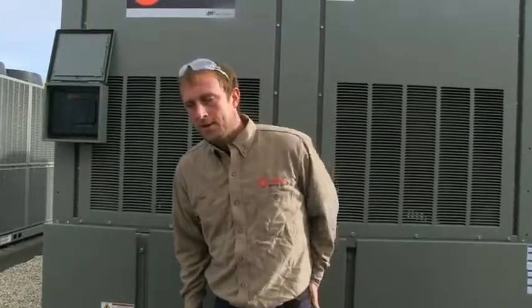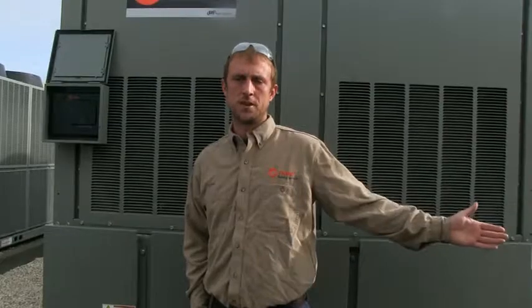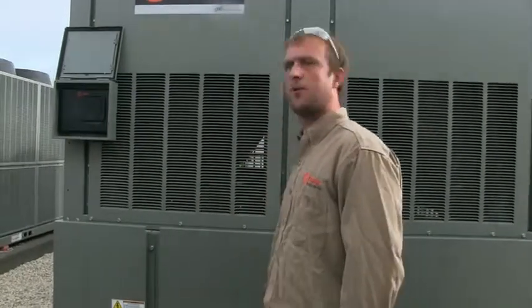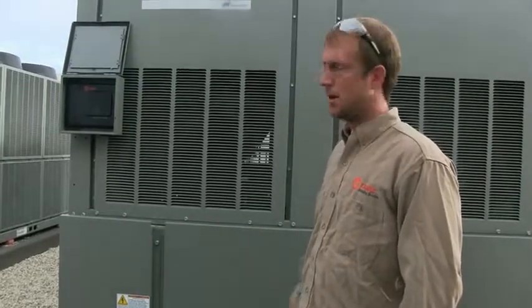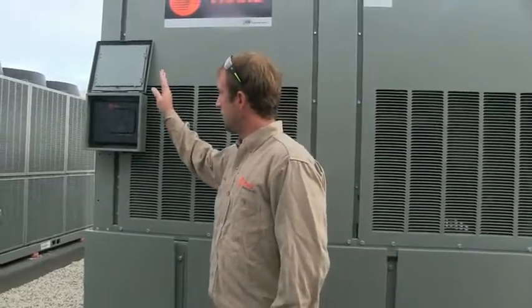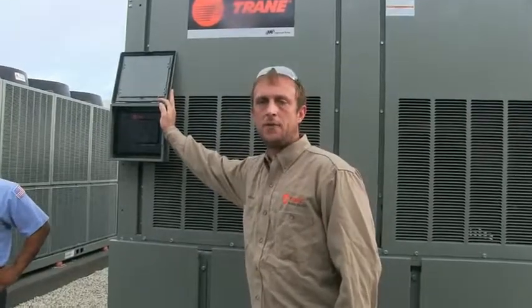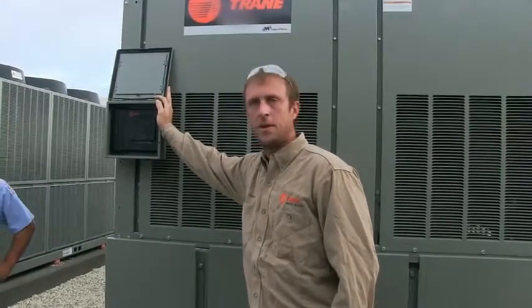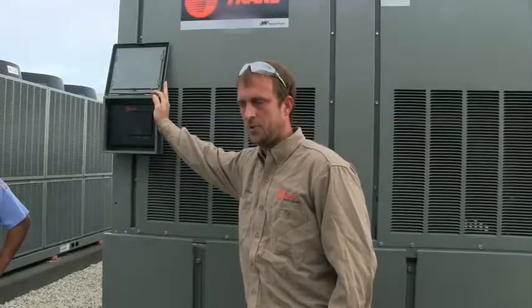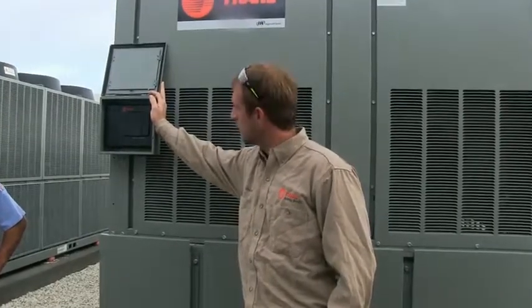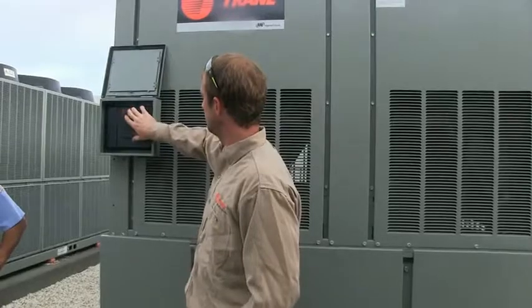Okay, what we have here is a Trane 130-ton chiller with scroll compressors, pump package. There's a VFD on the side of the chiller that controls the operation of the pumps. You've got across-the-line start for the compressors. Basically, this is the CH530 Dynaview module. This is the brains of the chiller. It controls pretty much the entire operation. I'll go over a few menu items with you here.